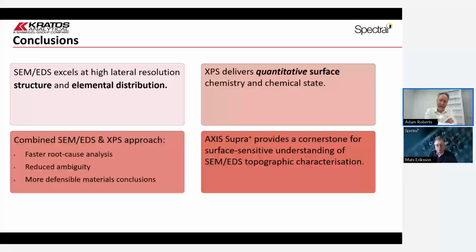The difficulty, obviously, for XPS is that the way we generate the X-rays in the lab, we use an anode with a particular coating, and that gives us X-rays of a characteristic wavelength or energy. And because we then monochromate, we're very limited to the combinations of X-rays that we can use in a lab environment.